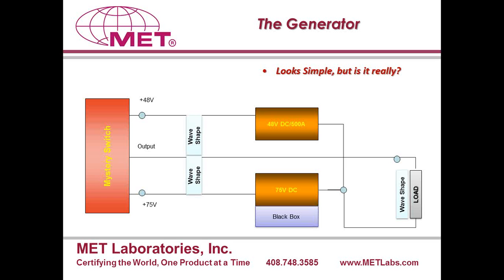So your generator has to have the flexibility to tune these networks according to the amount of current being drawn by the EUT. These wave shaping networks cannot be designed in a way that you choose one value and leave it there. They are a function of the current. If your current is in the range from 50 amps to 100 amps, you may have one setting. Going from 100 amps to 200 amps, you may have another setting, and so on and so forth. So you may have 3 or 4 different settings of these wave shaping networks, which will allow you to get the cleaner, correct waveform according to the standard.